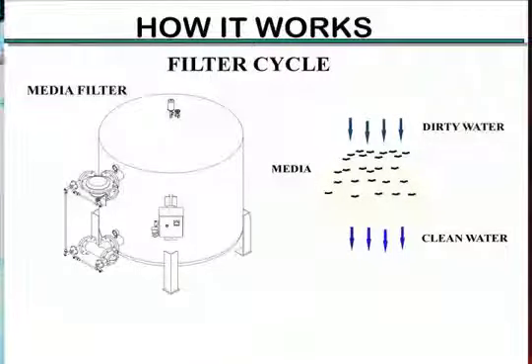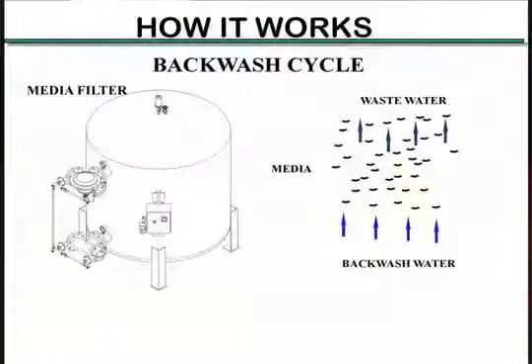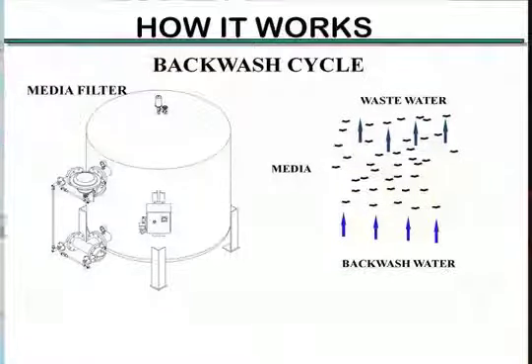In normal operation, loading it, the water goes through the media and comes out clean. The particulates are left in the interstitial area between the grains of whatever the media is. To backwash, the water runs the other way, comes back through the media. It lifts those particles up, or lifts the media up. The particles caught in the media get taken out, and then that water is taken out to drain somewhere and is taken out of the system. So the particulate matter gets taken out with it.